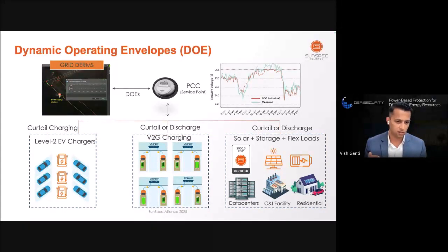Let's take a V2G charging depot as an example. When a limit is set, the chargers either have to curtail, or under certain conditions, have the ability to discharge back into the grid. So the control schemes and the concept are not new.